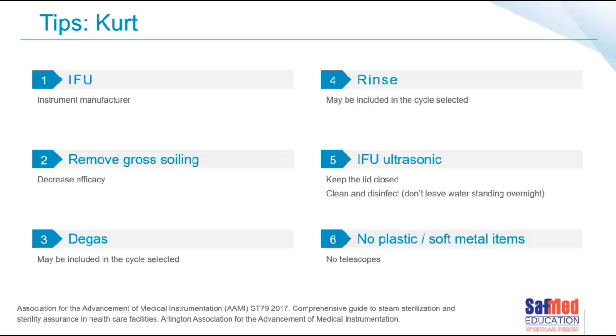So, if we use an automated one, for example, you and I know that with some of those you take the instrument, load it in the basket, start the cycle, and it'll go through 3 cycles. It'll do a pre-rinse, a main wash, and a rinse again. In those circumstances, you might get away with not having to rinse too much, maybe. But certainly, if you're trying to reuse the water, or you've got a semi-automated system, and you've got a whole lot of debris on the instruments themselves, from what I understand, that almost dampens the efficacy. Is that correct of the ultrasonics?